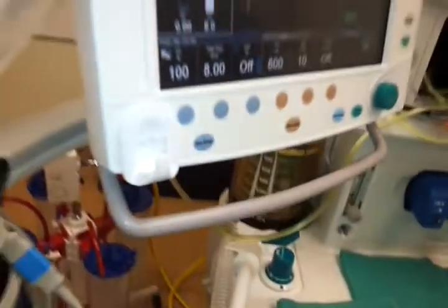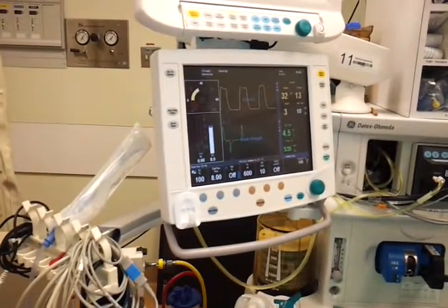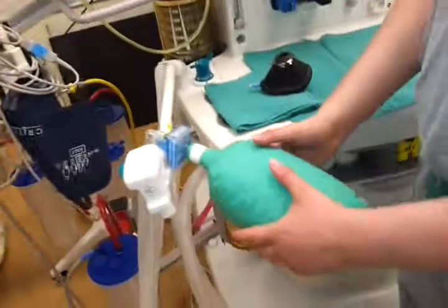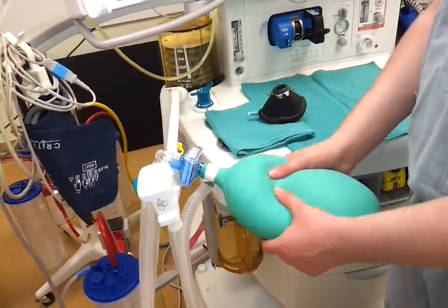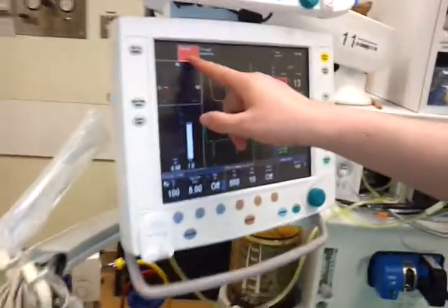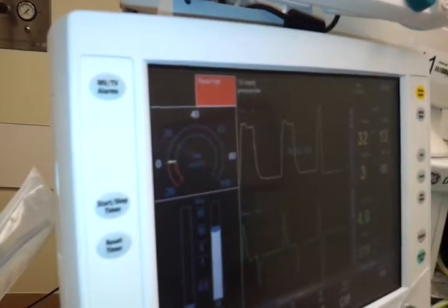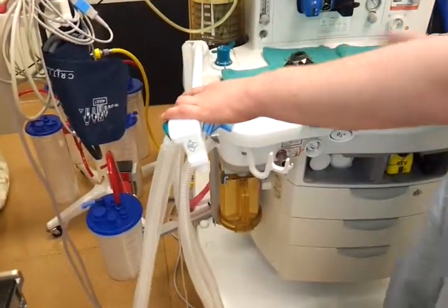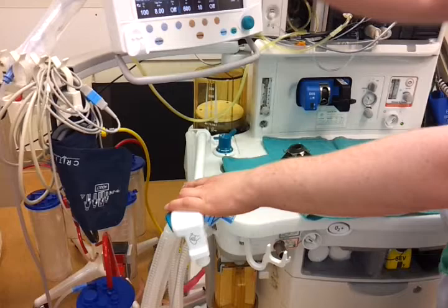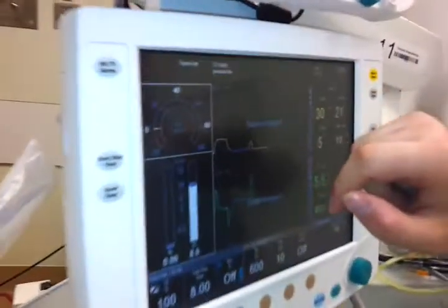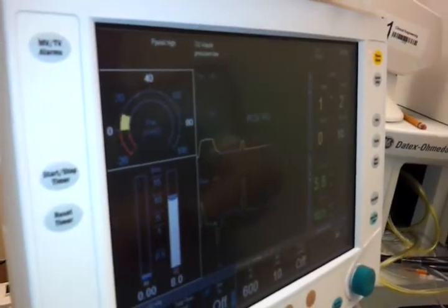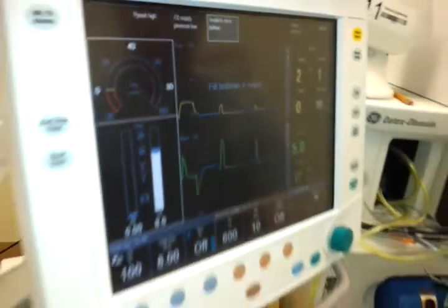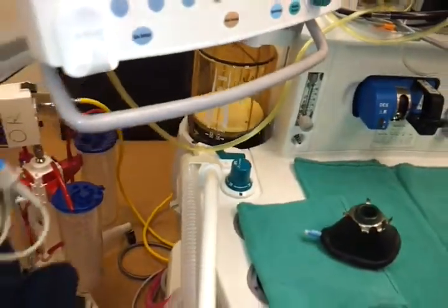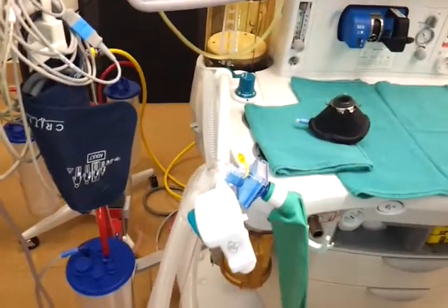So basically you have to do a high pressure, a low pressure, and an apnea test. For the high pressure, you're going to take the bag, and when they take a breath in, you're going to squeeze it. So create a really high pressure. So high pressure. And to get the low pressure, basically you just disconnect the bag, and after a few breaths, the bellows will completely empty. You should be able to see it up here in a second. So unable to drive bellows. So that's the low pressure test. There's a big leak. We're going to switch it over to bag to test the apnea alarm.